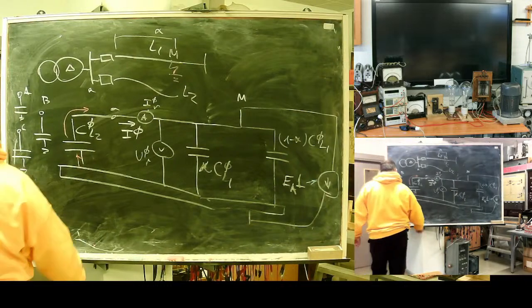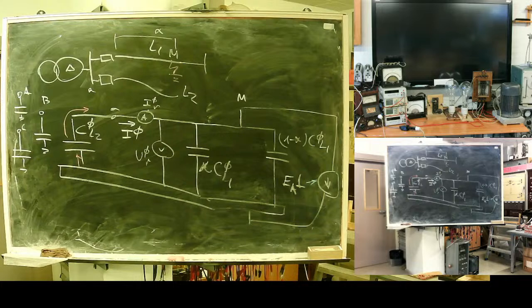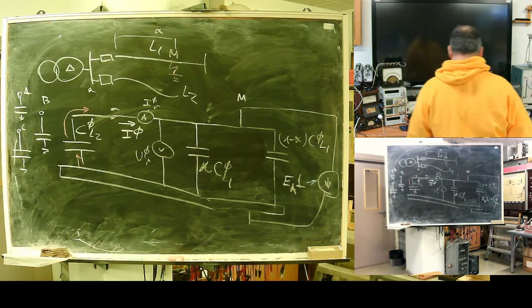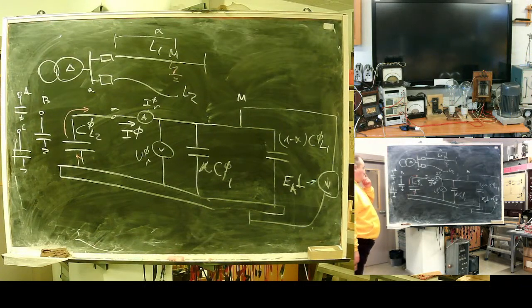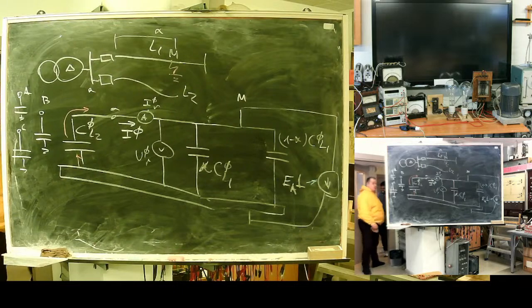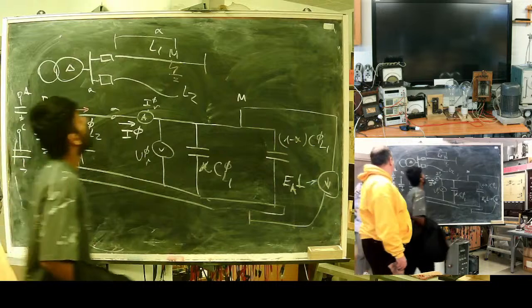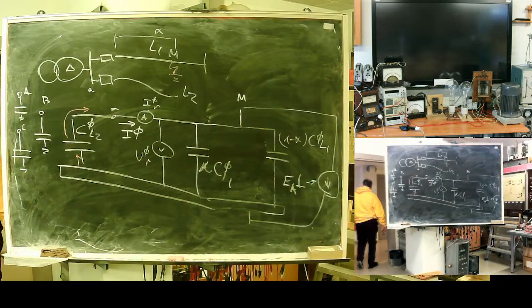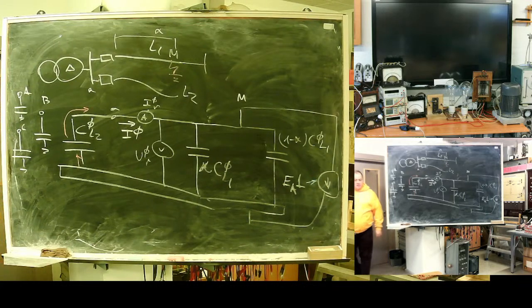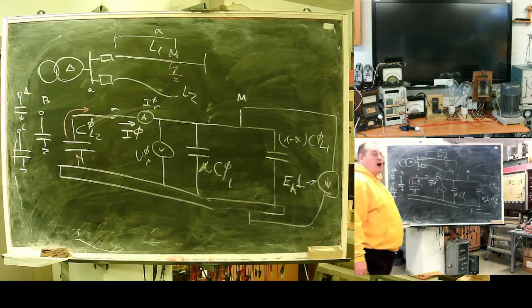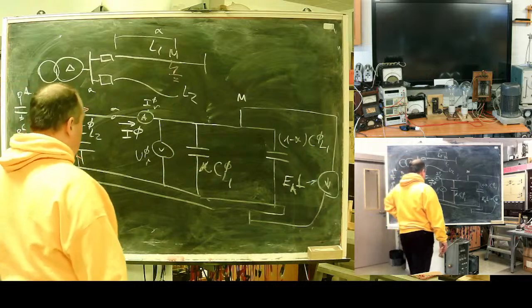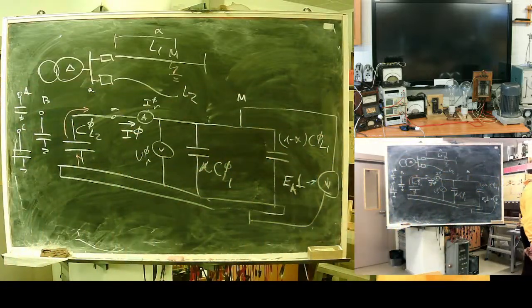It's important to understand this when we speak of such protections. How can my schematics look like? Here I speak of protection for isolated neutral networks. And one of the very important moments is that the current through the protection relay is determined not by the fault place, but by the capacitance of the healthy part of the network.